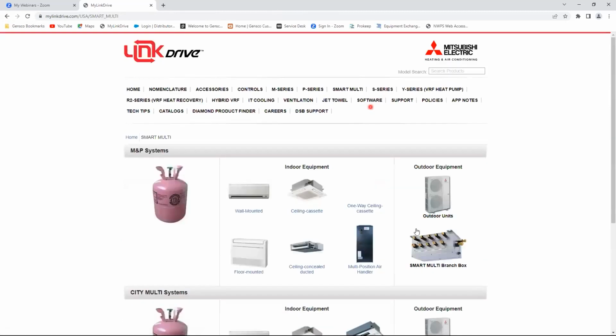We have our smart multi-units, our new smart multi-units, where they combined our MXZ branch box systems and our PUMY S series. So the smart multi, out of the box, comes set up as an S series PUMY. If you are installing M series indoor units with your smart multi, you will need a branch box, and you will need to turn on SW2 dip switch number 5 in the outdoor unit to tell the outdoor unit that you have M series heads and that you have a branch box connected to it.